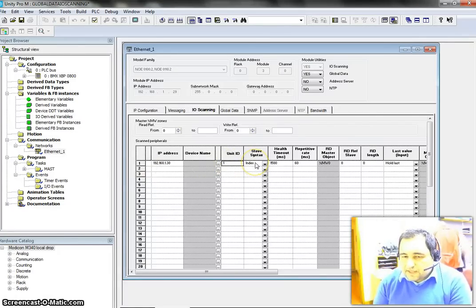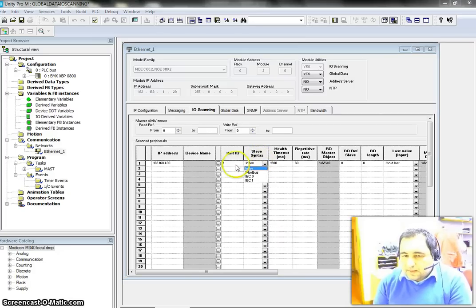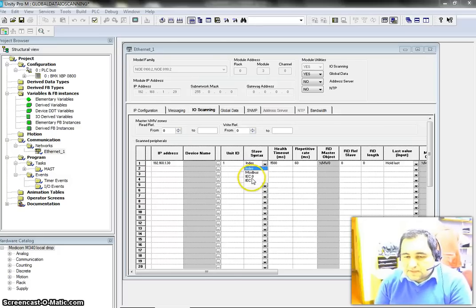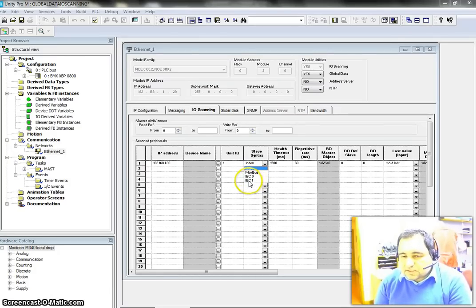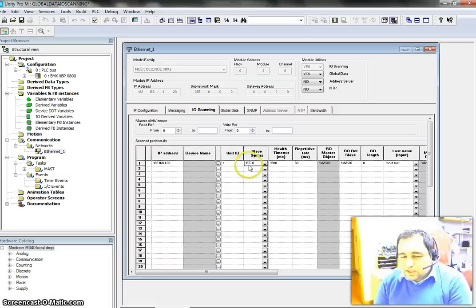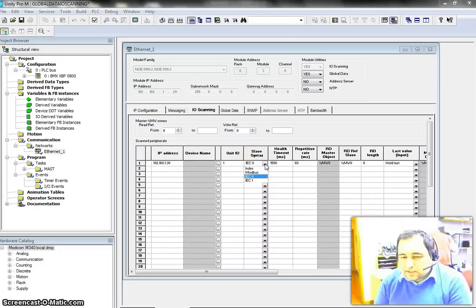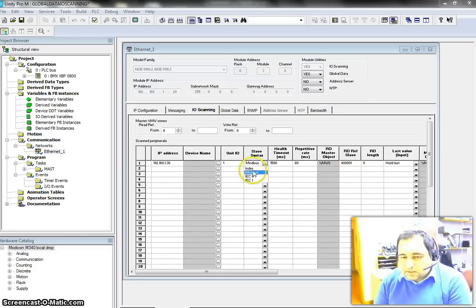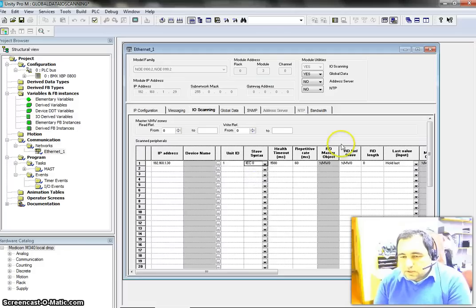After that, we have a slave syntax — we can have it as an index, or we can change it to Modbus or IEC standard. There are two IEC standards: one starts registers with 0 and another starts registers with 1. In Unity Pro we use IEC 0. If you use Modbus, the number is going to be something like 40001, because Modbus starts with 1. So let's go back to IEC 0.